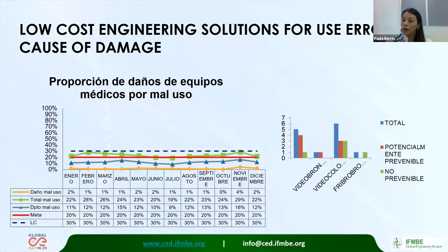And we realized that the high maintenance cost for this cost of damage was related to our flexible endoscopes. So we started a specific measure of failures in our flexible endoscopes, and we proposed a process change. That process change, in the transport and the reprocessing of the device, led us to diminish about 80% of the expenses in distal and impact damages, with an investment of about 11%.